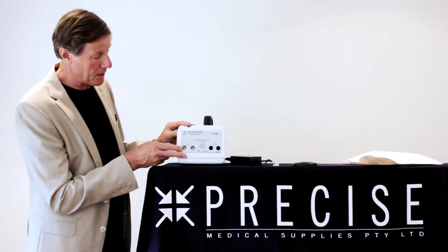Turn the pump around and you will see that there are a number of ports on the back here. Now the first two to note are these two here. They take the pneumatic foot switch that comes with the instrument. When you buy this particular pump, you get two pneumatic foot switches, and that's quite useful because it means that you can have a foot switch on either side of the bed, so you don't have to keep flinging the foot switch from one side to the other. For demonstration purposes, I'm just going to use one foot switch, and that just pushes in there, just a push fit like that, so that's ready to go.